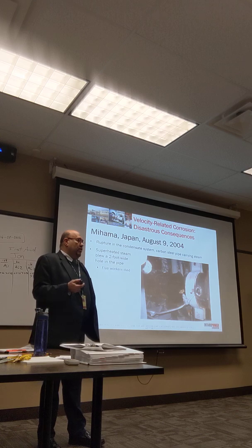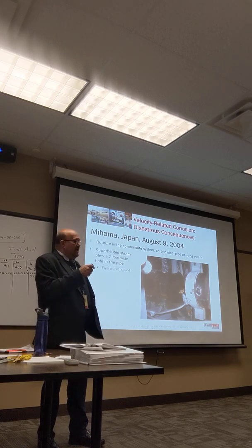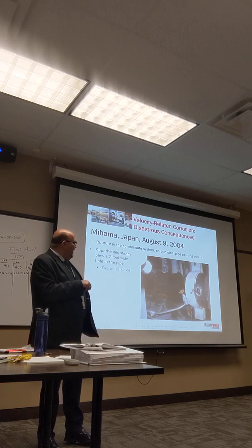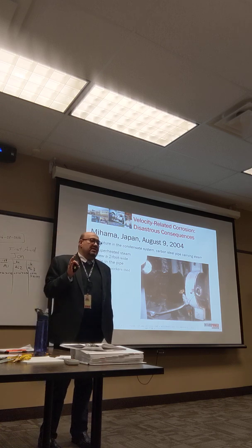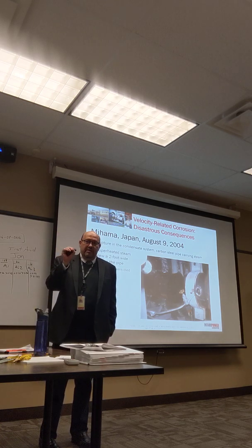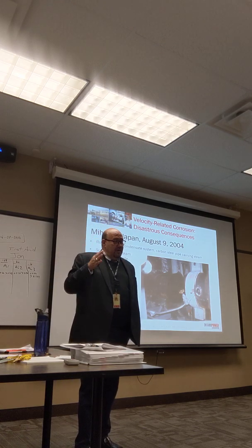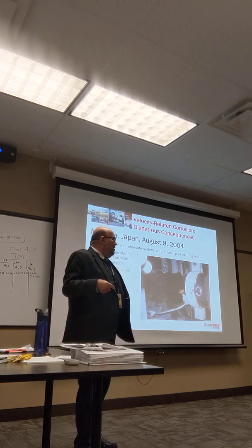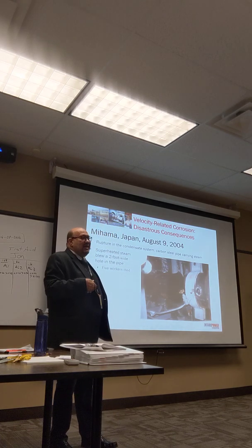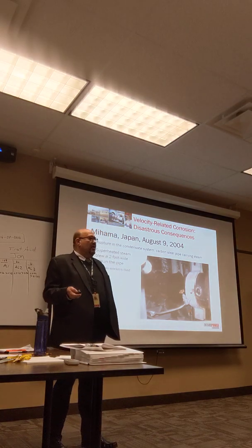I was involved for a little while at Bruce Power doing calcs, where the FAC expert would say, assume this part really fails, or this part becomes ineffective. What is the minimum thickness that we need? When they measure and find they're approaching this minimum thickness, they can make an operational or maintenance decision to change. That was pretty useful for the industry, just a wake-up call.